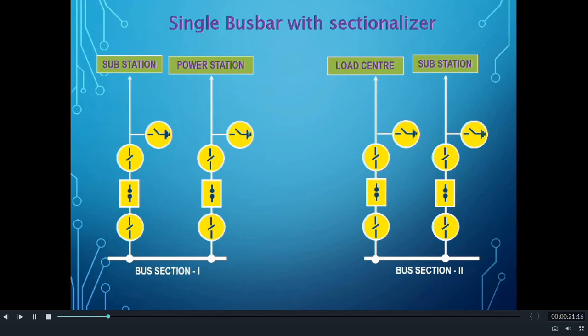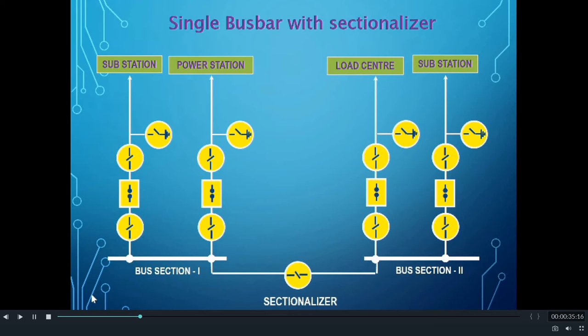In this scheme, the busbar used in a substation is only one. However, there will be two sections of the busbar — Bus Section 1 and Bus Section 2 — and these two bus sections are mutually connected through a Sectionalizer. Sectionalizers are generally provided with an Isolator and sometimes with a Circuit Breaker and Isolator on both sides.